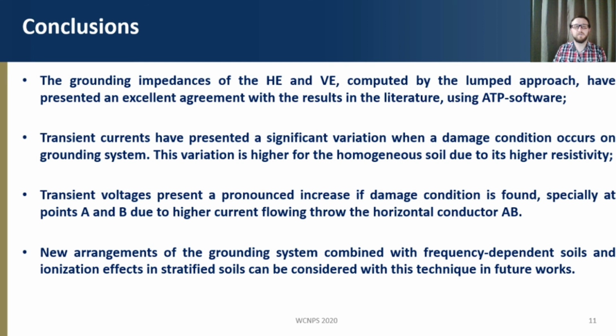As conclusion, the lumped parameter approach can be used to represent horizontal and vertical electrodes and be incorporated in ATP software. The currents presented a significant variation in the damage condition. Transient voltage presents a pronounced increase in the damage condition. As an advantage of this approach, we can represent any arrangement of ground system and consider the frequency dependence of the soil parameters, other layers of soil, and ionization effects, which can be considered using the lumped representation for the grounding system.